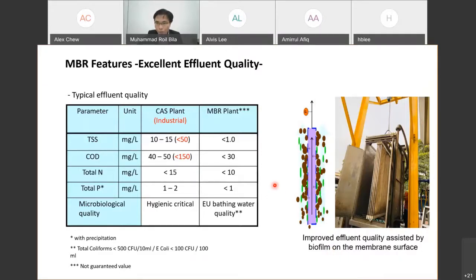In MBR we have to pump the water from outside, go inside the modules basically, and when it has to go inside the module, it has to pass this biofilm. And this biofilm also needs food, and it also consumes the organics. So apart from giving a problem to the filtration, it also helps to increase the effluent quality. That is why in almost all reports that compare activated sludge to MBR, they will claim universally that MBR effluent quality is way better than activated sludge.